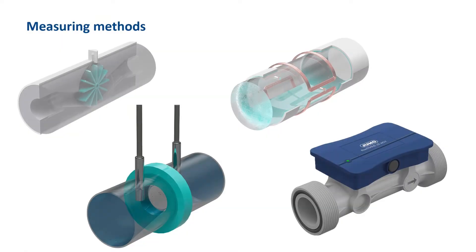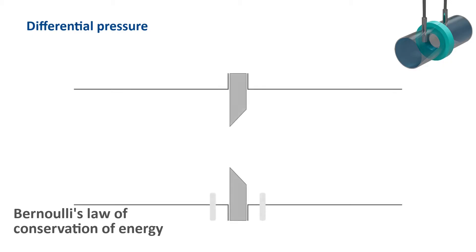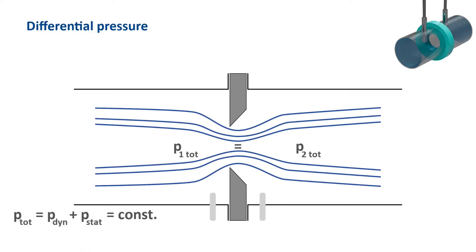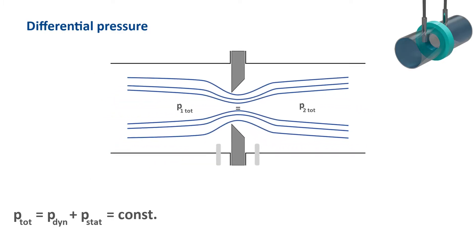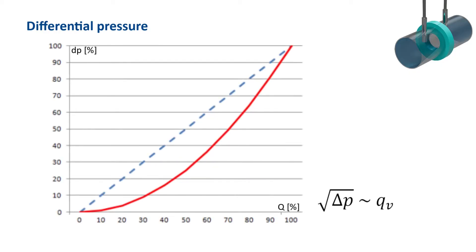In the differential pressure method, the flow velocity is calculated via the differential pressure. The total pressure is composed of the dynamic pressure and the static pressure. According to Bernoulli's law of conservation of energy, this total pressure is constant within a closed system. By tapering the pipe cross-section at one point, the flow velocity is increased there. As a result, the dynamic pressure component increases and, since the total pressure is constant, the static pressure component decreases. The static pressure is measured immediately before and after the cross-section taper, and the pressure difference is then a measure of the flow. The flow rate has a quadratic proportional relationship to the measured differential pressure, which can then be root extracted in the pressure transmitter.